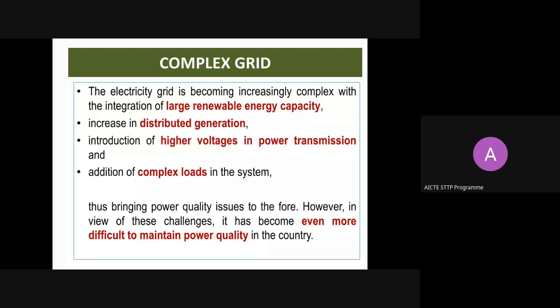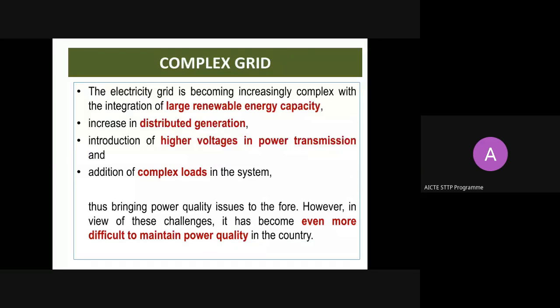The second point is distributed generation. It is not at a particular location; across the entire grid, generation is distributed at different locations. That also increases the complexity of the grid. And in those days, the voltage level would be 11 kV, 22 kV, 33 kV, or 110 kV. But now it is 110 kV, 230 kV, 400 kV, and nowadays even 765 kV. Higher voltages are used in the power transmission system.